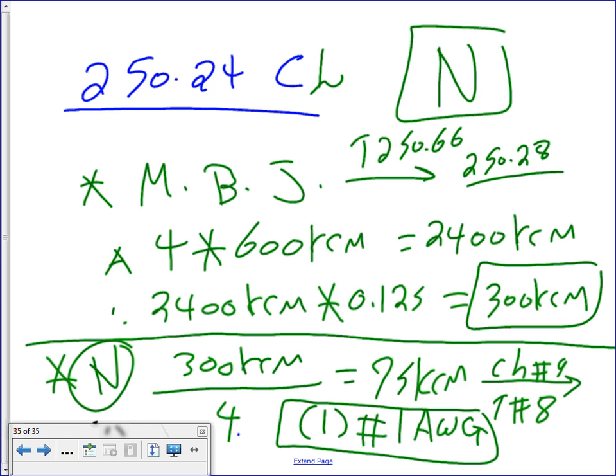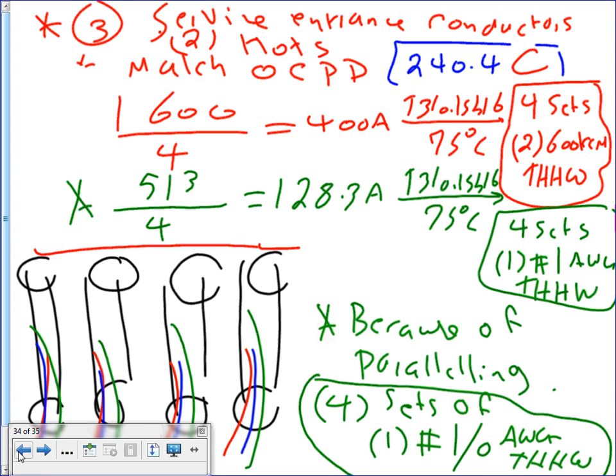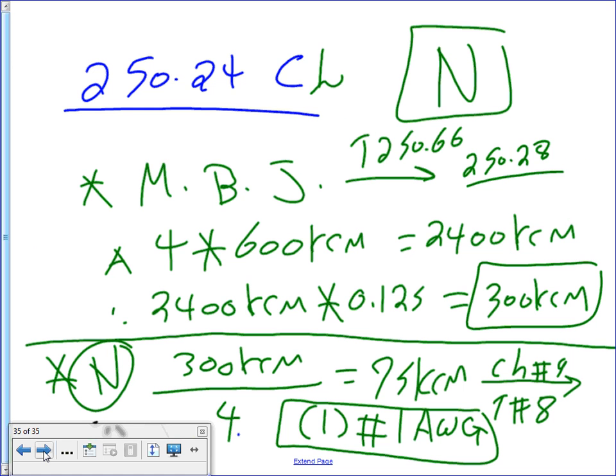One conductor, number 1. Have I paralleled? What was my size to start with? My size we started with was number 1 anyway. So I'm okay here, and I'm okay because I'm not smaller than the main bonding jumper. But because we parallel, we jump up to 1 aught. So long story short, guys, if the number you came up with here is 2 aught, the neutral has to be 2 aught.